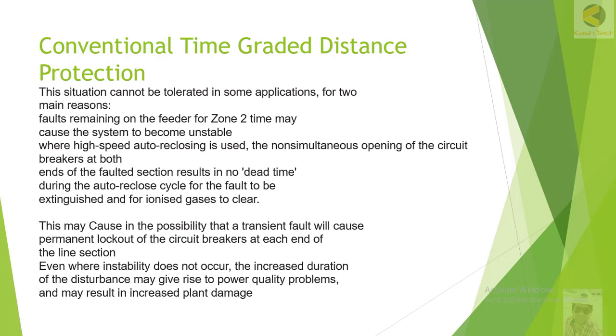The first reason is that a fault remaining on the feeder for Zone 2 time may cause the system to become unstable — because of a large fault current causing a power swing, which may result in tripping of breakers elsewhere. The second reason is that where high-speed auto-reclosing is used, the non-simultaneous opening of breakers at both ends of the faulted section results in no dead time during the auto-reclose cycle for the fault arc to be extinguished and ionized gases to clear. This may cause a transient fault to result in permanent lockout of the circuit breakers.